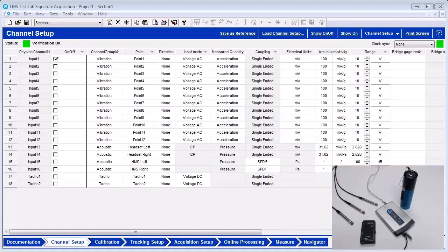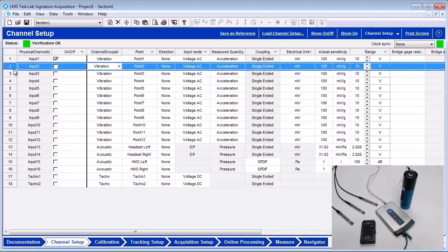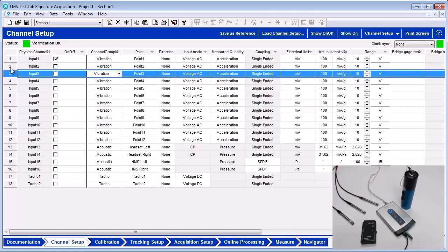Let's begin with the calibration of a single ICP microphone. Select the channel setup worksheet. Each row corresponds to one channel on the SCADAS. Attach the microphone to the first dynamic channel on the SCADAS front end using the appropriate cables.